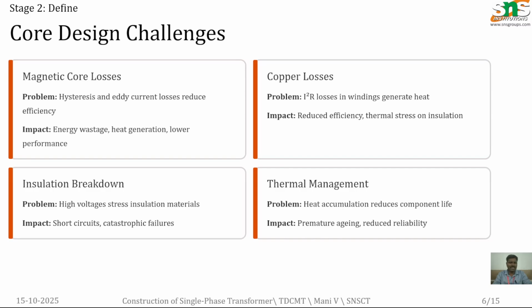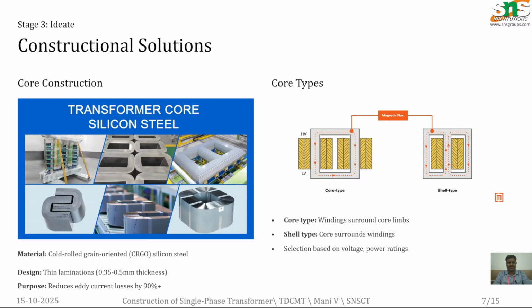If the copper loss gets high, the efficiency also gets reduced and heat generation is also high, which affects the insulation. If heat is produced in the system, the winding insulation may break down. So in order to avoid the heat produced inside the transformer, we have to handle the heat accumulation, because otherwise premature aging occurs and reliability can be reduced. These are the challenges faced in the single phase transformer.